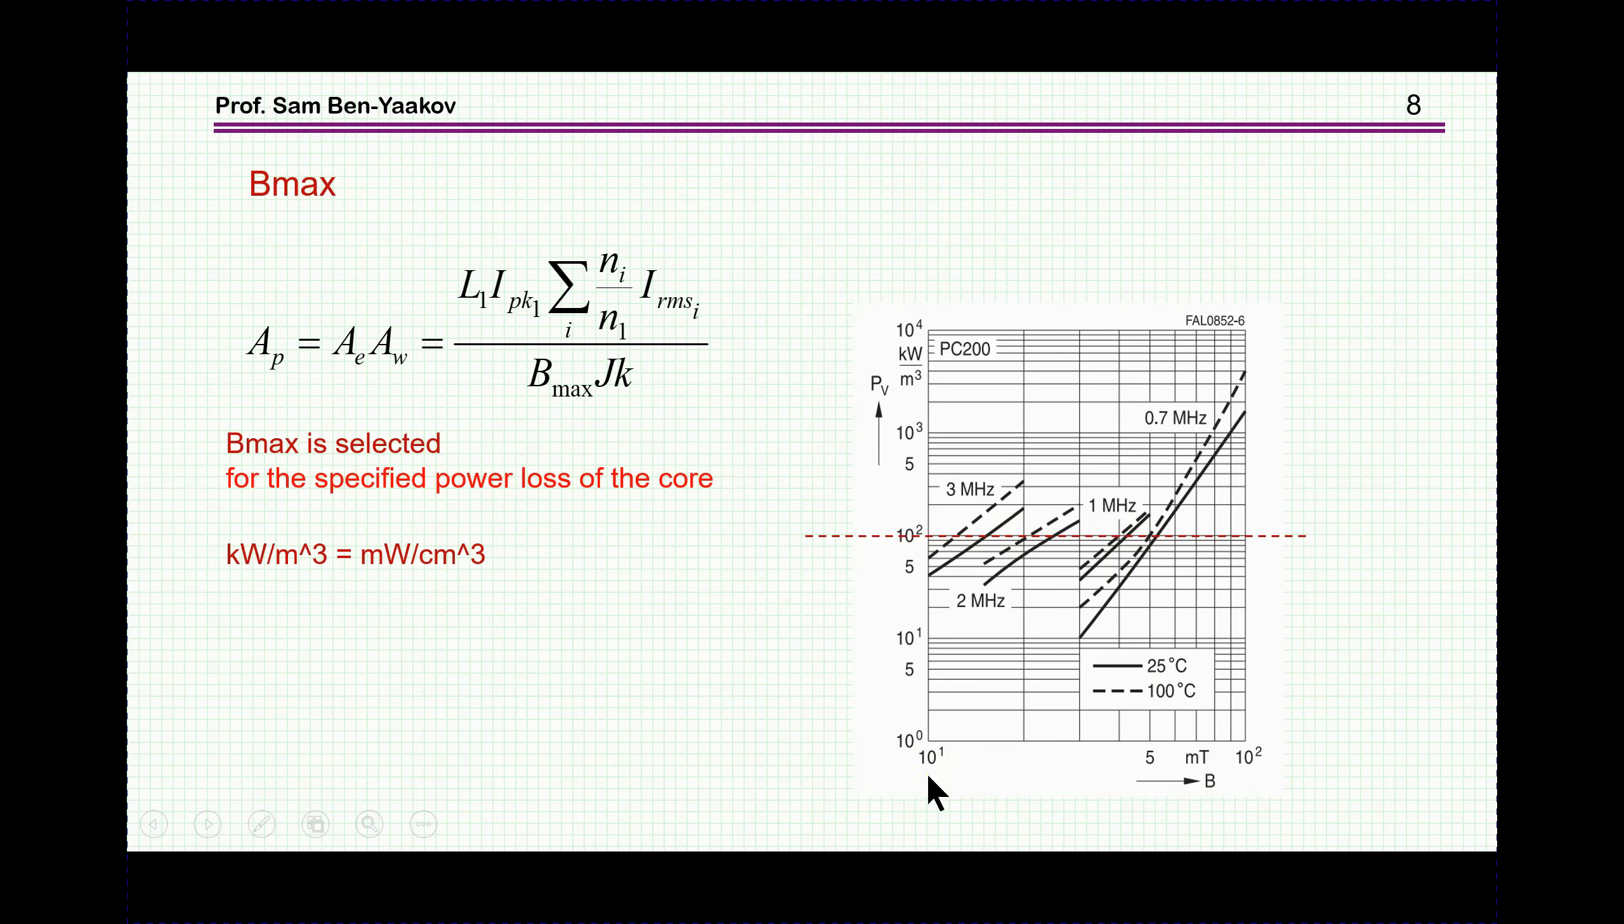This is actually a parameter that allows one to select a core. You can go to a catalog, a datasheet, and find out what is a core size that will meet the specific requirement for your converter. Let's have a look at this expression and see how does it relate to frequency, which is the subject matter of this presentation. I_peak and etc. are related to the design of the converter, the power level, voltage, turns ratio. So if I design the converter to one frequency or another, these will not change.